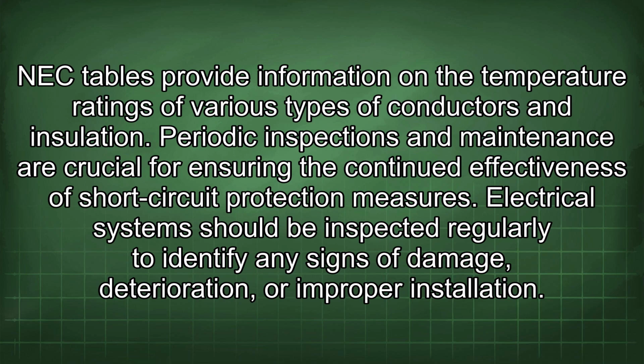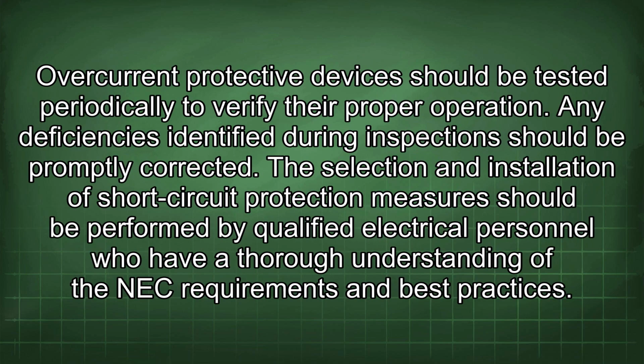Periodic inspections and maintenance are crucial for ensuring the continued effectiveness of short-circuit protection measures. Electrical systems should be inspected regularly to identify any signs of damage, deterioration, or improper installation. Overcurrent protective devices should be tested periodically to verify their proper operation. Any deficiencies identified during inspections should be promptly corrected.